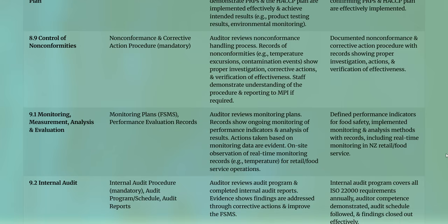And then in clause 8.9, requirements for the control of nonconformities. This is a mandatory requirement. You must have nonconformance and corrective actions procedures. The auditor will review the nonconformant handling process during stage 1 and records of nonconformities, for example, temperature excursion or contamination events, showing proper investigation and corrective actions and verification of effectiveness.